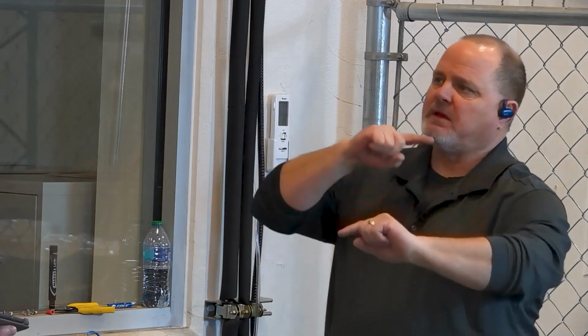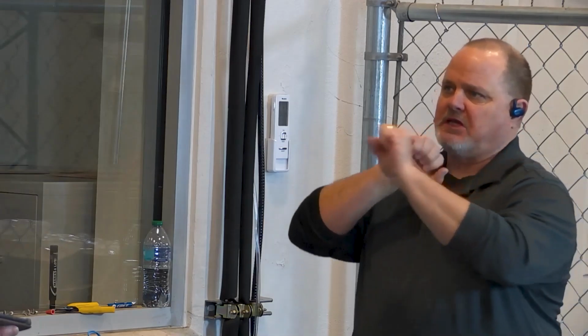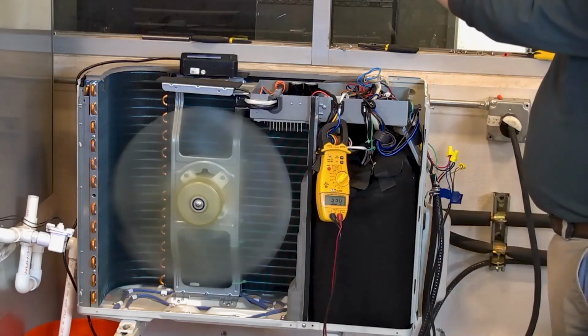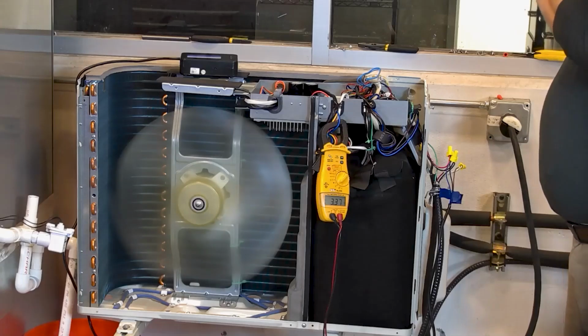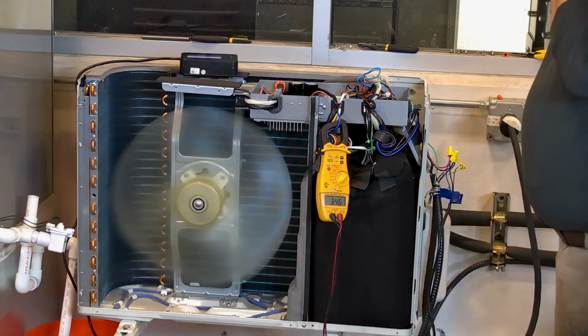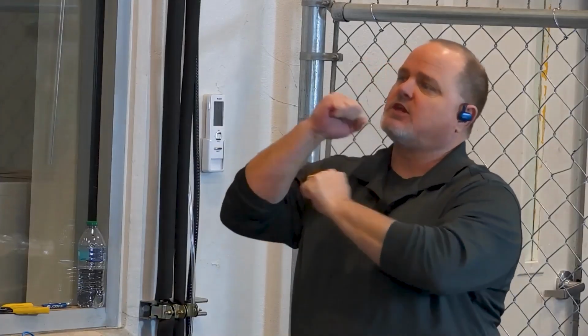What happens, and let's say not a full restriction but a good partial restriction, is that compressor is trying to work up against that. You've got a three-phase motor in there trying to spin up against this ungodly pressure that it's not liking. So it could actually go out on a phase problem or desynchronization because we can't get the refrigerant to flow. Right. Not because there's anything wrong with the compressor.